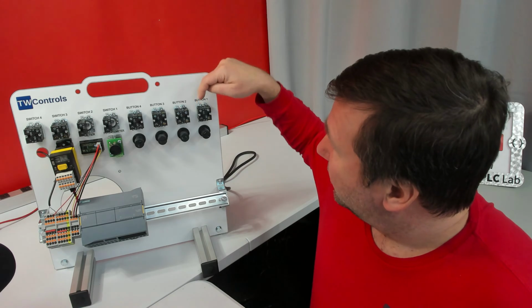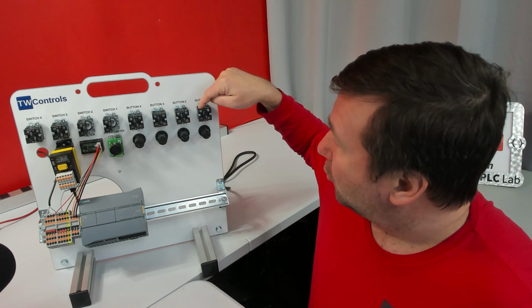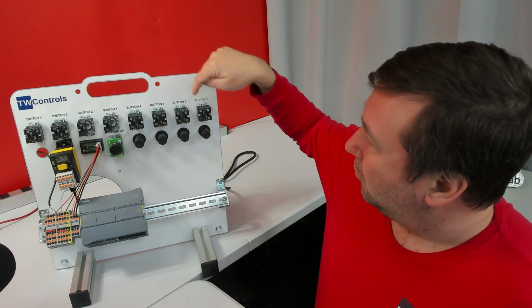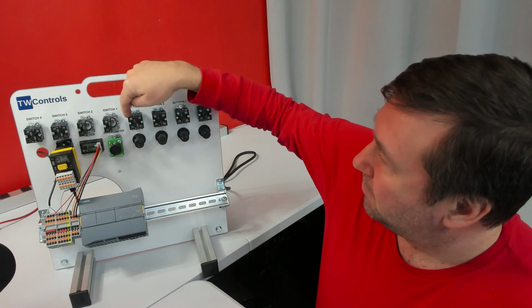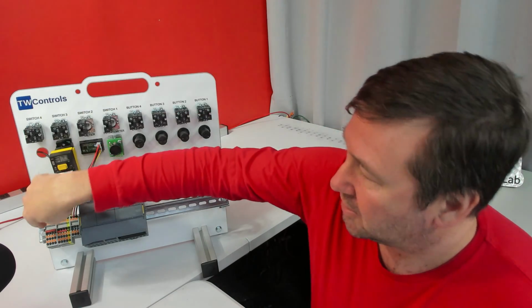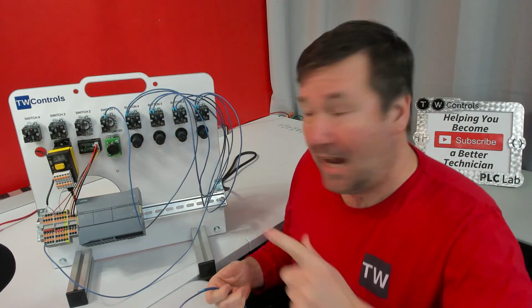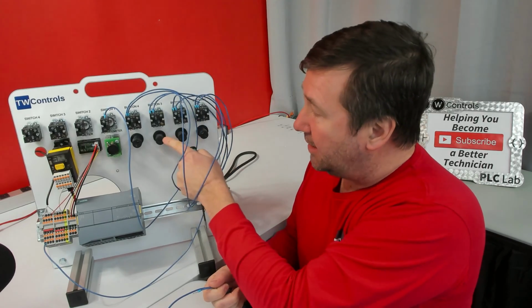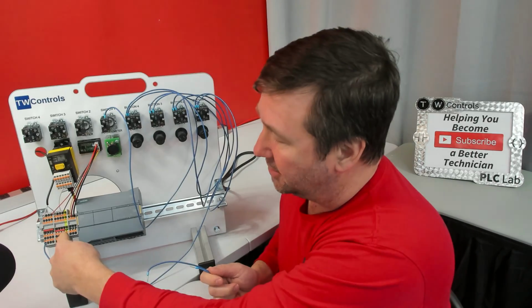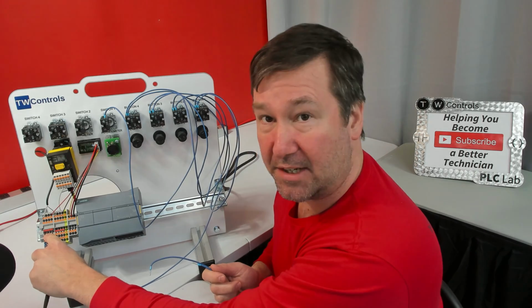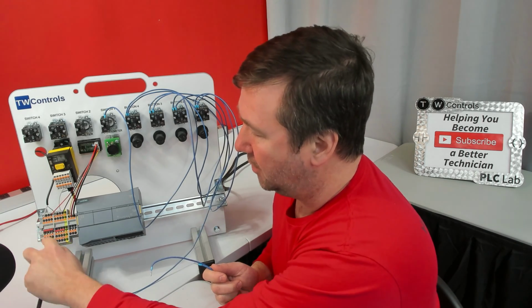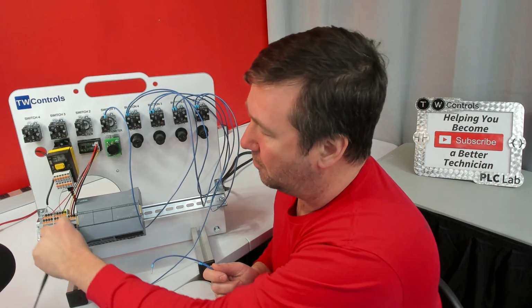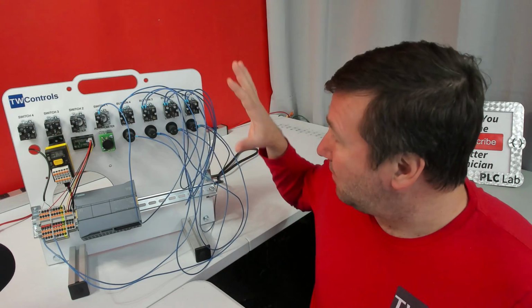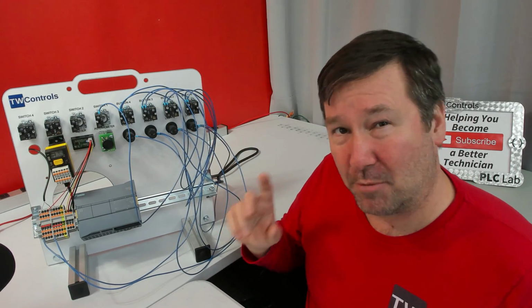But to begin with, we're going to jumper the green or normally open contact of button 1, button 2, button 3, button 4, and switch 1 to our plus 24 volts. Now I'm going to jumper one side of each of my lights to the minus 24. And remember, the left set of terminal blocks is our plus 24 volt, and the right set is our minus 24 volt.